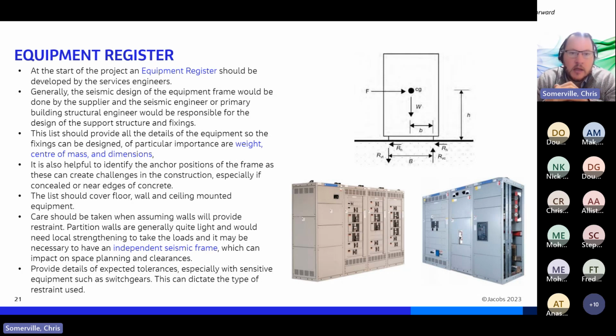The keys here are knowing the fixing points for the base as well. This can dictate issues, especially if you've got an air handling unit positioned right next to the edge of a slab with set fixing points, which could cause problems getting those fixings to comply. Looking at those issues early, we might need to put in a plinth or something cast in to resolve it.